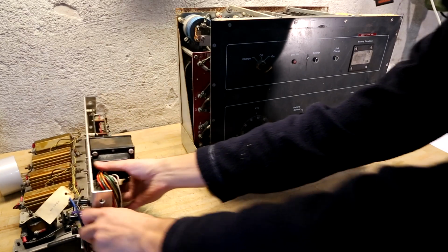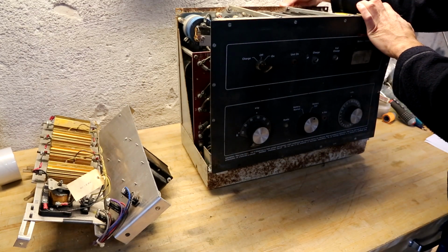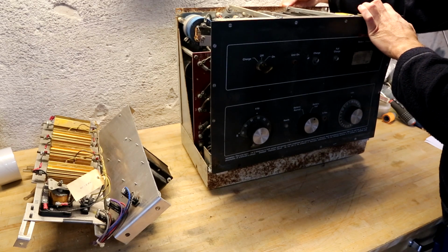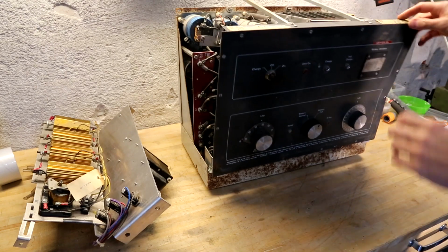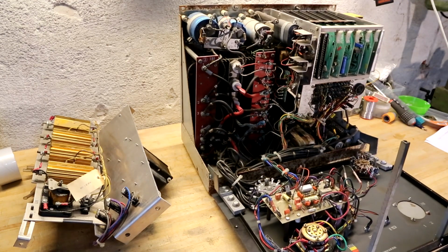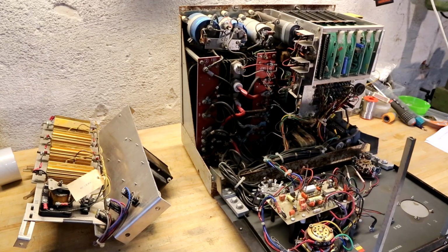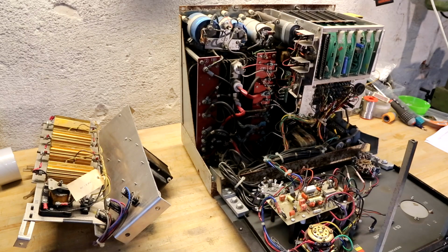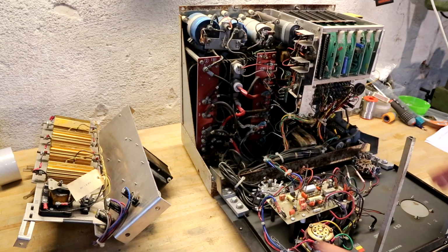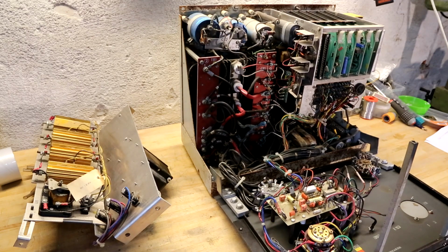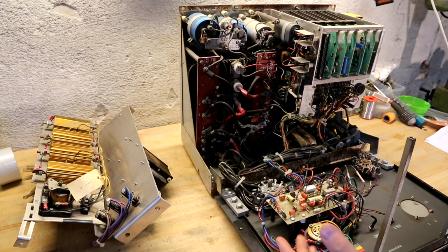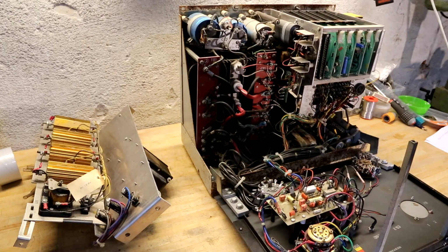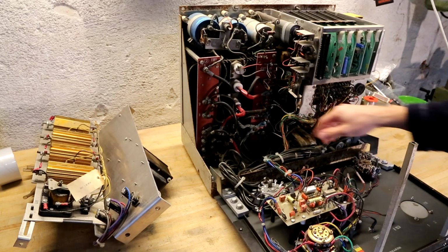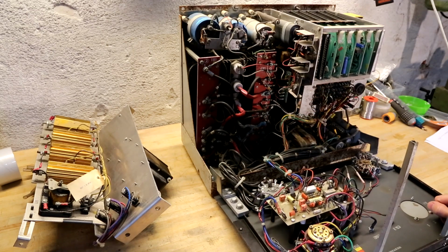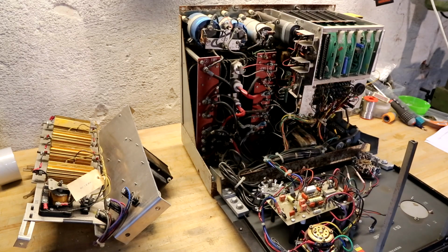This unit is of course made from a time where everything should be serviceable. So if we just remove the screw holding the whole front panel here, it opens just nicely. And everything is actually completely possible to exchange. There's a little bit of control here at the front, along with all the selector switches and the little board here. But the whole power inverter section and the controls up here, along with the capacitors, is actually accessible. The only things that are hidden behind are the huge power transformers and some relays and power resistors, and those are generally things that do not break.